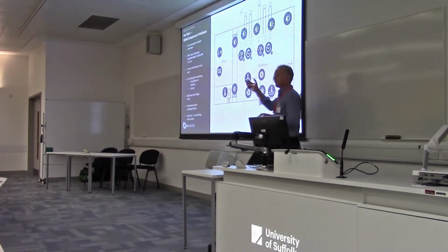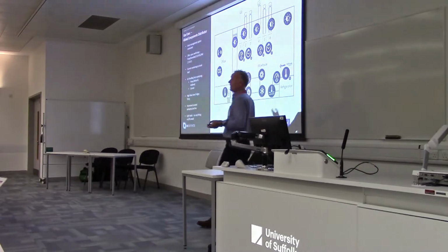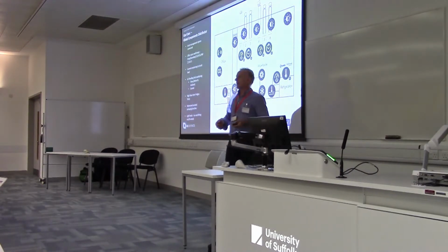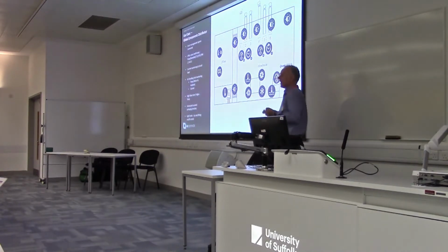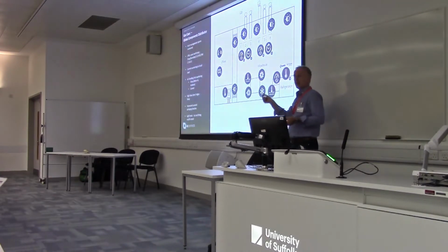All of these devices used to get serviced all at the same time, on the same day, every year. You'd think that was all right. But the truth of the matter is, they didn't need that, because it was only the first three that ever got used. But to try and keep it simple, they'd had people coming in to look at IoT applications. All we did was monitor the current usage on the main supply to each of the six devices. By monitoring the current, we know whether it's in use or not, and then we log the number of hours that it's in use.